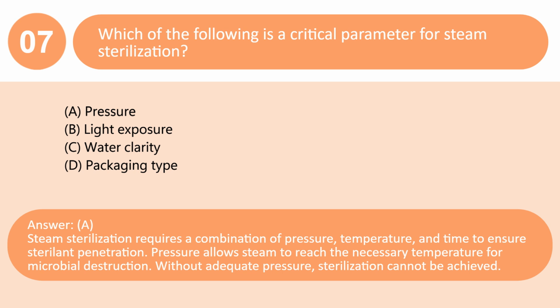Pressure allows steam to reach the necessary temperature for microbial destruction. Without adequate pressure, sterilization cannot be achieved.